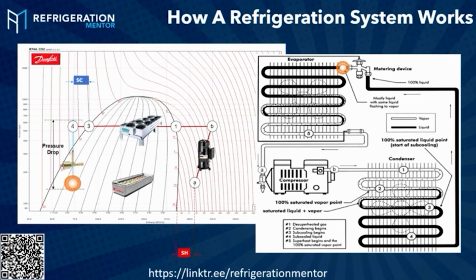So we're taking this high temperature, high pressure liquid, and we're dropping that pressure. Make sense? You guys all know this stuff, which is great. And so now we drop that pressure off. It starts to flash through this metering device, and now we get some flashing happen. And then we get into the next part, which is our evaporator.